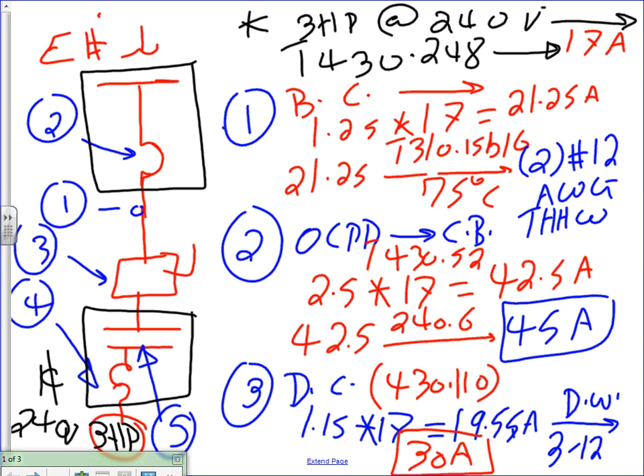How do I know it's 30 amps? They don't make 20s. Disconnect. These are the ones that are on the wall right here. That's exactly what the one on the wall. These are 30 amps. Can I use the circuit breaker as a disconnect? Yes. We could have used that circuit breaker if it's within sight as a disconnect.